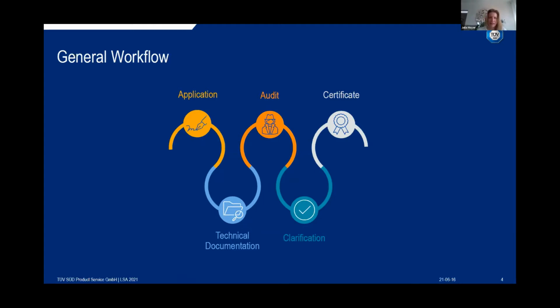Technical documentation, experience, everything we have then learned about your product shall then go into the audit setup and audit planning. Usually, for the initial audits, it's a two-step approach. First, more or less a document review and a check if the manufacturer is ready for us to go on site for step 2. In some cases, if we don't know you, we need to go on site with the first step as well. Then, as you may have experienced, there are clarification rounds. There might be findings, there might be open questions and so on. It is an iterative process. And at the end of the day, if all is well, there's the certificate.